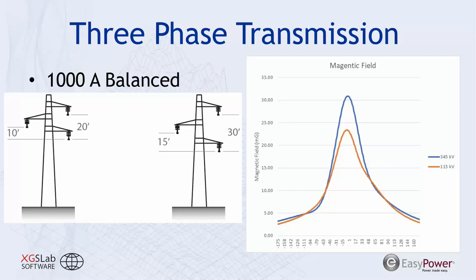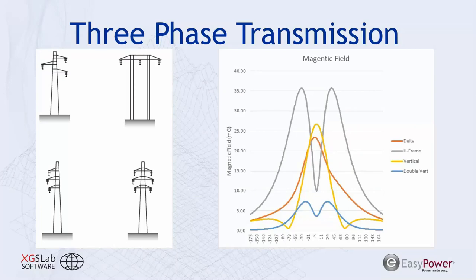And it should not be a surprise to say that when you change the geometry of those phase conductors, you're dramatically affecting what that magnetic field looks like along the right-of-way. So again, we have our orange line representing our delta transmission line configuration. Our horizontal or H-frame configuration is represented by this gray line, and we can see much greater magnetic fields along the right-of-way. And this is because we're not seeing as much phase cancellation or magnetic field cancellation between each of these phases.